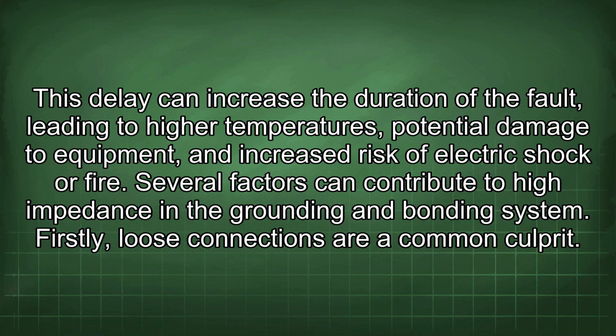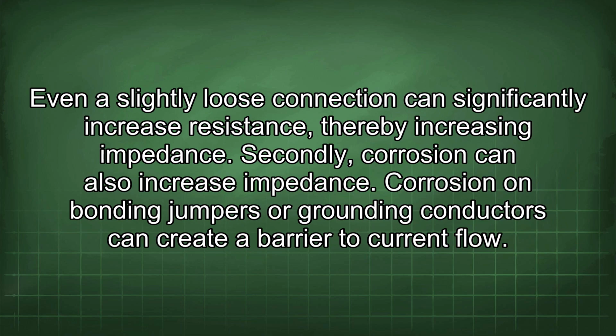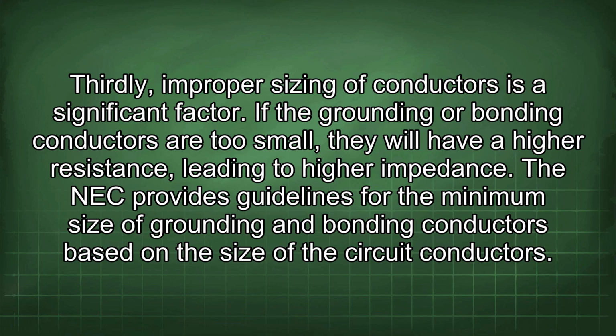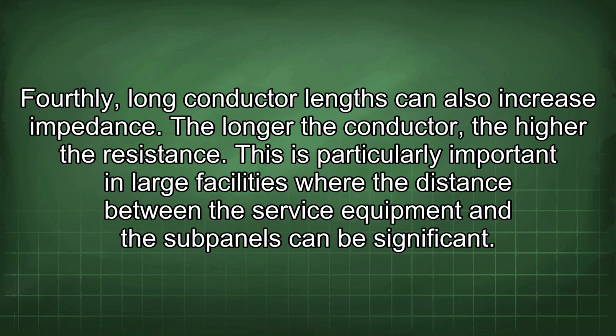Several factors can contribute to high impedance in the grounding and bonding system. Firstly, loose connections are a common culprit. Even a slightly loose connection can significantly increase resistance, thereby increasing impedance. Secondly, corrosion can also increase impedance. Corrosion on bonding jumpers or grounding conductors can create a barrier to current flow. Thirdly, improper sizing of conductors is a significant factor. If the grounding or bonding conductors are too small, they will have a higher resistance, leading to higher impedance. The NEC provides guidelines for the minimum size of grounding and bonding conductors based on the size of the circuit conductors. Fourthly, long conductor lengths can also increase impedance. The longer the conductor, the higher the resistance. This is particularly important in large facilities where the distance between the service equipment and the subpanels can be significant.